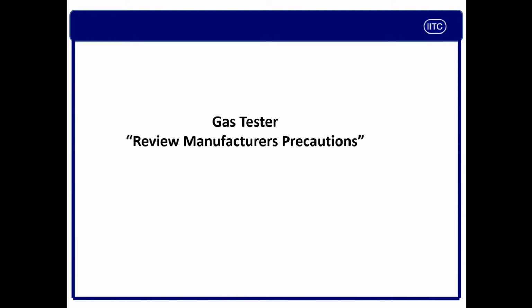And the second very important thing is different types of warnings which may apply with the instrument. One is oxygen deficient or enriched environment may cause wrong LEL reading. You must know that if the area is oxygen deficient or enriched, then it may cause wrong reading of LEL because it may be a combustible type of sensor. Point number 2, ensure sufficient battery charge before use. You must ensure that your battery is completely charged, otherwise you are starting the pump for 5 minutes but the pump is not efficiently working.